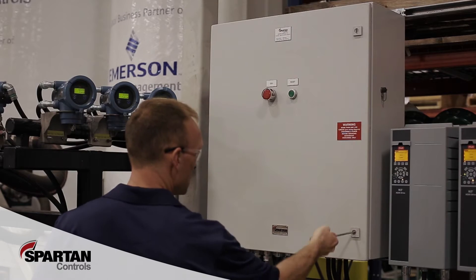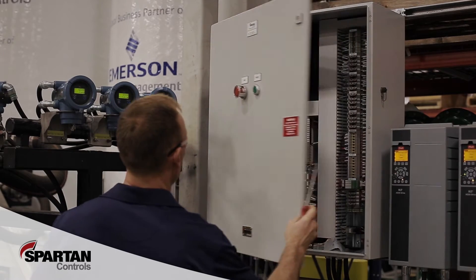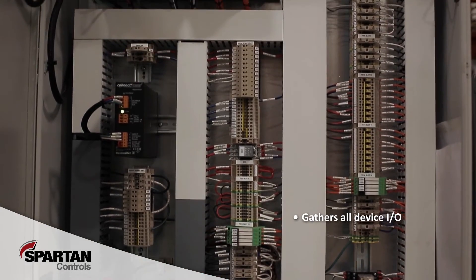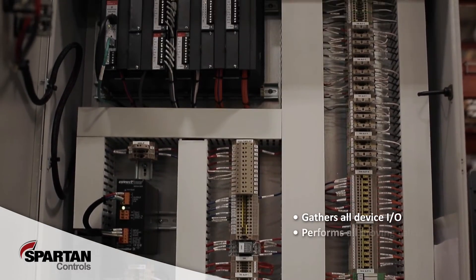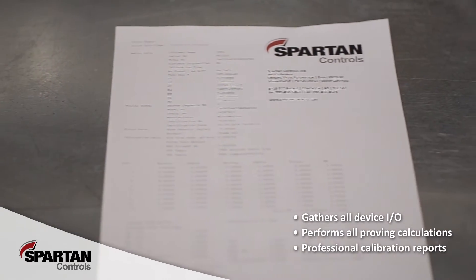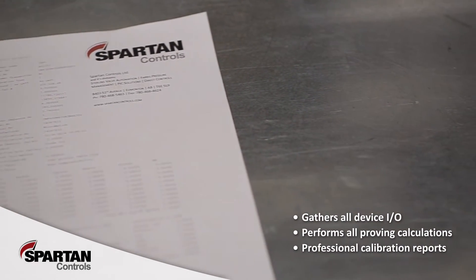By utilizing a sophisticated ROC800L proving flow computer, our master meter proving skid gathers all device IO, performs all proving calculations, and creates professional calibration reports that are stored to a customer profile database.